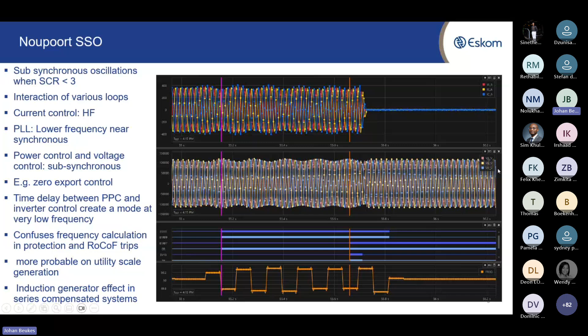As soon as it dropped below 3, the SSO started to happen. The RoCoF relay, which looks at the rate of change of frequency, not really SSO, picked it up as an exceedance, and it tripped. And there you can see in the current and voltage waveforms at that plant what happened. The current dropped to 0, and when it dropped out, the voltage was stable again. So that was one case.